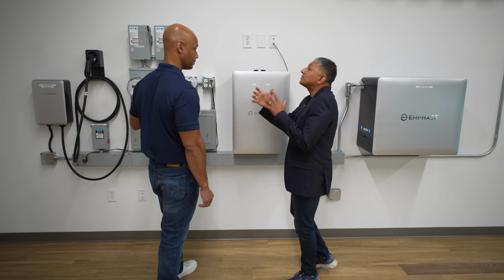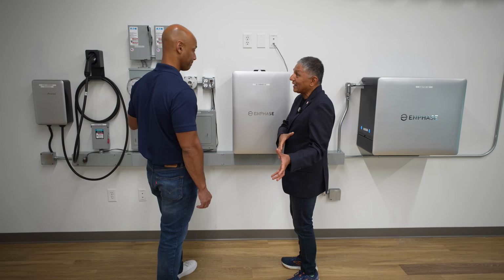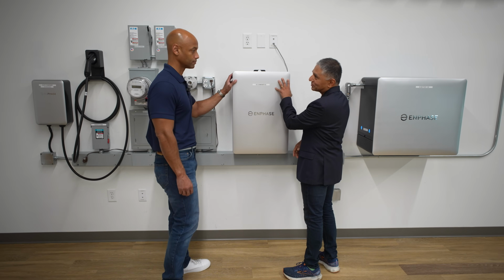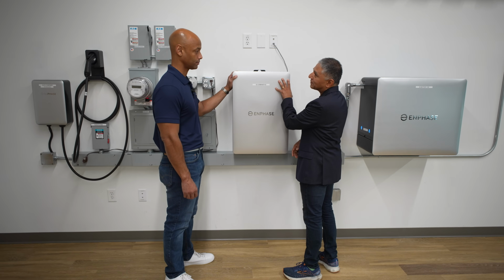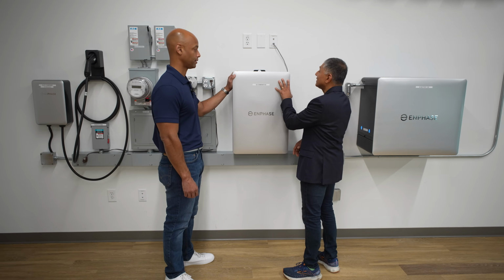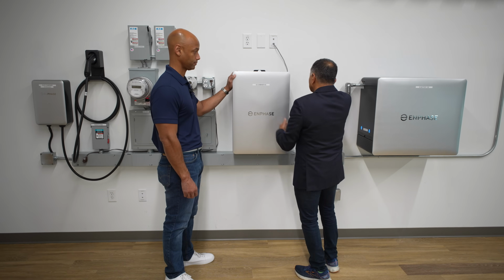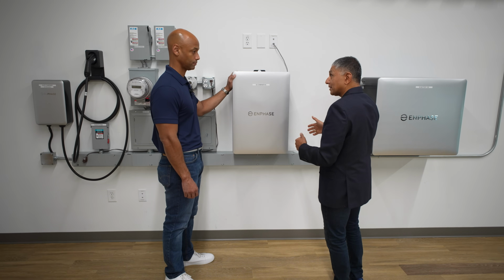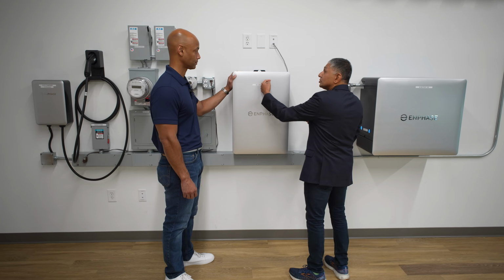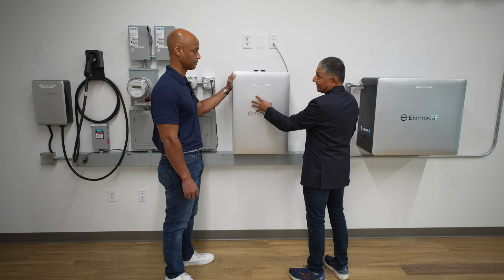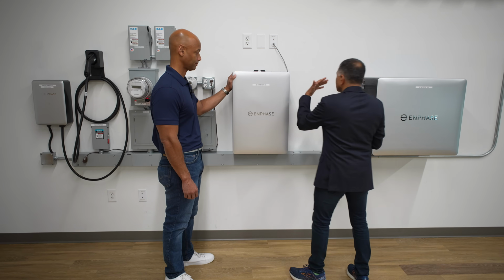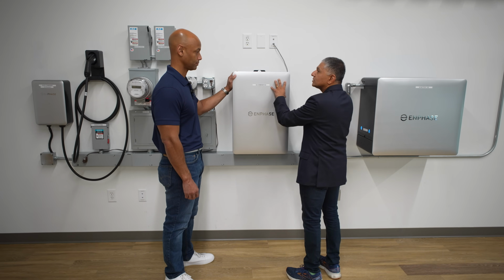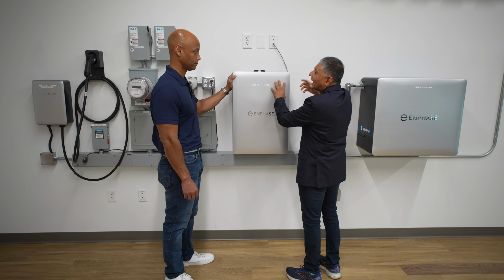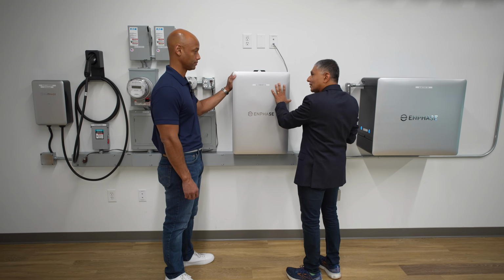Because the 120% rule does not necessarily apply, because we have what's called power control system. So we have bus bar PCS that ensures that we are never overloading, say, a 100 amp bus bar, even if there's a 100 amp source from your DERs. Because the system looks at the output of this, looks at the generation from the grid, and ensures that you're never overloading. If it's a 100 amp bus bar, never more than 100. If it's a 200 amp bus bar, no more.